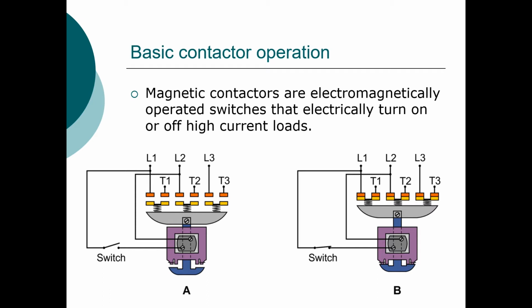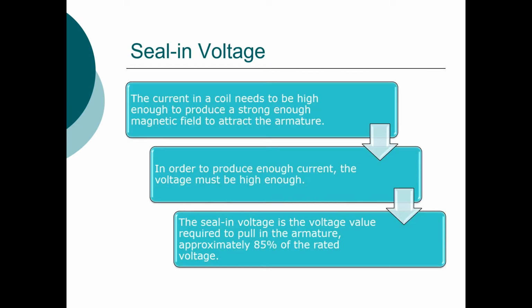The contacts are isolated from the coil, so circuits at different voltages or current ratings can be switched using the contacts. The magnetic strength of the coil is dependent directly on the current running through it, which in turn varies with the voltage applied to the coil. In order for the coil to have enough magnetic strength to overcome the armature spring, we need to make sure we have enough voltage. This voltage is called the seal-in voltage and is typically about 85% of what the rated voltage is.